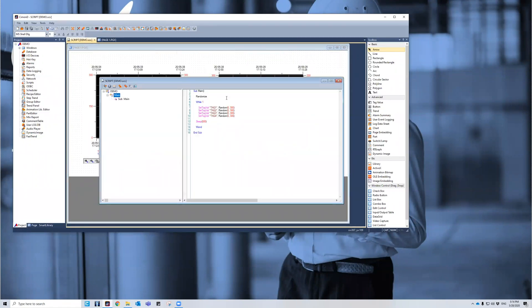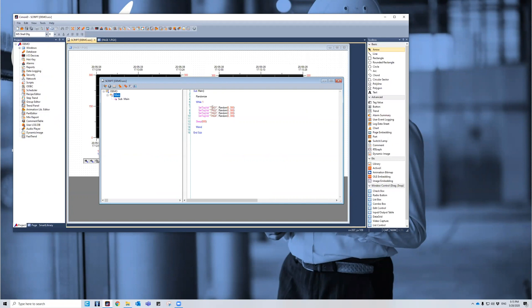And then I'm going to go to the script and show you what script I'll be using for this demo. So I chose sub main because this script will start running upon initialization of the project itself. It doesn't require a push button to start it or anything. This will be a randomizing script. So it will randomize the tags one through four, between zero and 300. It will sleep for 800 milliseconds. And it will continuously do this because of While 1 until we shut down the project.